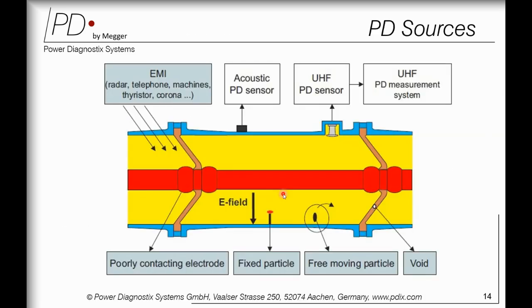So when we talk about partial discharge in the GIS, there might be different PD sources present in your electrical asset. These are a few examples which I'd like to highlight, taken from one of the technical papers published. In the GIS, you can see this is my HV enclosure, this is my HV conductor, and this is my support insulator. There might be some moving particle left in your GIS, some voids in your support insulator.